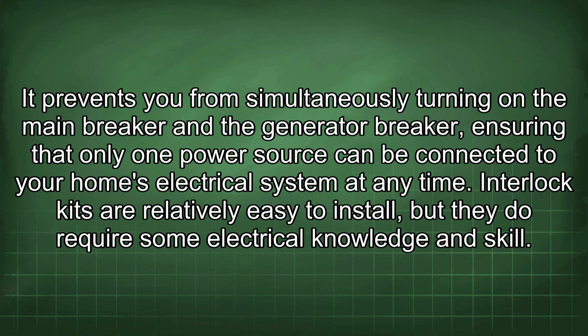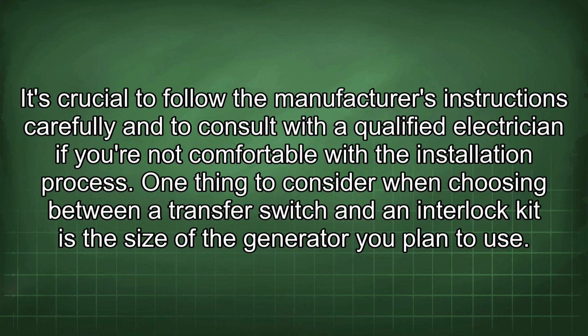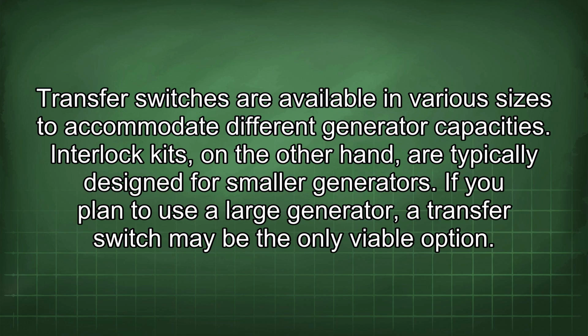Interlock kits are relatively easy to install, but they do require some electrical knowledge and skill. It's crucial to follow the manufacturer's instructions carefully and to consult with a qualified electrician if you're not comfortable with the installation process. One thing to consider when choosing between a transfer switch and an interlock kit is the size of the generator you plan to use. Transfer switches are available in various sizes to accommodate different generator capacities. Interlock kits, on the other hand, are typically designed for smaller generators. If you plan to use a large generator, a transfer switch may be the only viable option.